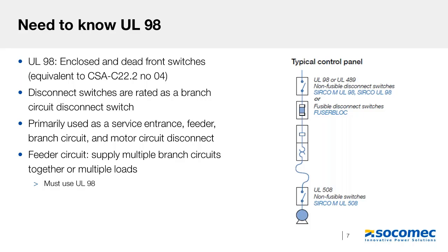So in the picture on the right, you can see that the UL98 disconnect goes at the top of the circuit, and an electrical installation is made up of these feeder circuits and branch circuits. The feeder circuits supply multiple branch circuits together or multiple loads, while the branch circuits supply just a single load, such as a motor, lights, a transformer, things like that. So feeder circuits must utilize the UL98 switches, and these branch circuits can use either UL98 or UL508 switches. So bringing it back to the poll, you can see now that for feeder circuits, you need to use a UL98 switch.